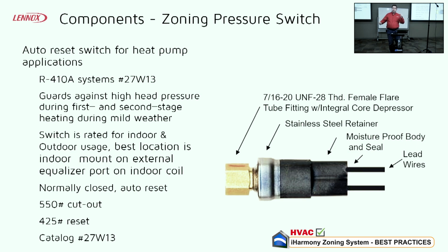As I talked about before, that discharge air sensor is running the show. It's looking at that discharge air temp. So as that airflow reduces, your discharge air temp is going to go up, and then your pressure in your outdoor unit, your discharge pressure, is going to go up. This switch is meant to monitor that and say, hey, my pressure's going up. It opens at 550, before the switch in the unit does, to tell the zone board, hey, my pressure's getting too high, I'm fixing to cut out on high head pressure. That tells the zone board to either stage the compressor down or shut it off so that it doesn't lock out, and then we're stuck without heat pump heat without having somebody come out and reset it.